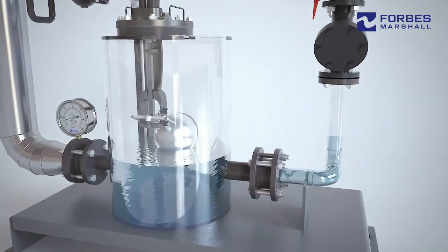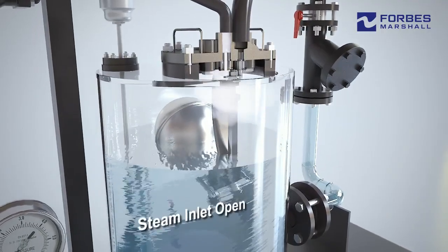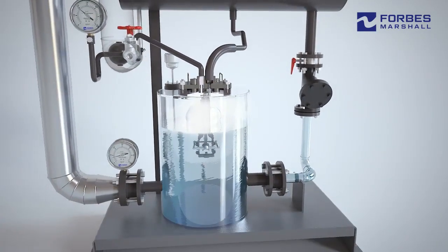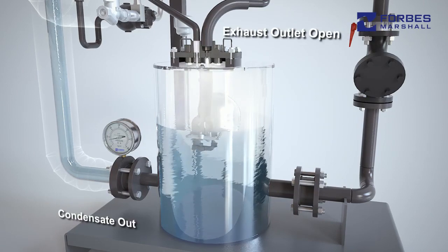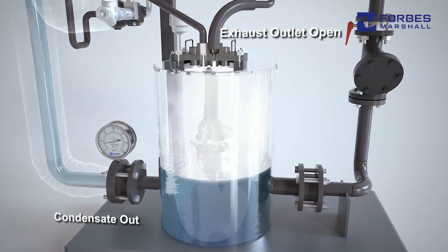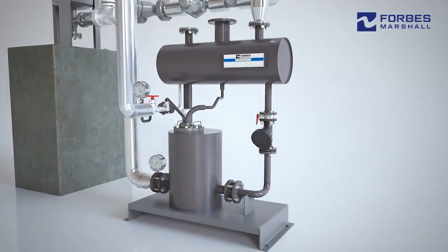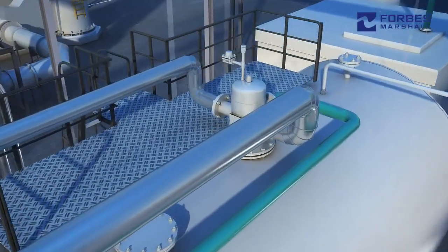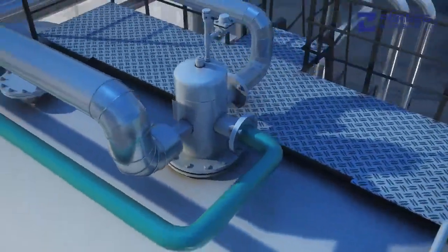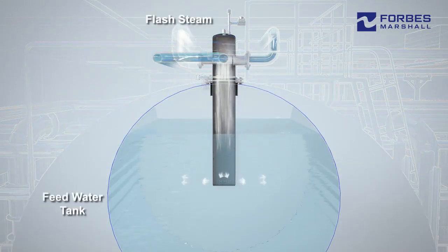The condensate is pumped using only steam as the motive media. A pump uses 3 kilograms of steam for pumping 1 ton of condensate. Condensate recovered offers secondary benefits such as reduced thermal shocks and superior response time for boilers. A condensate recovery meter provides clarity on the condensate recovery factor.